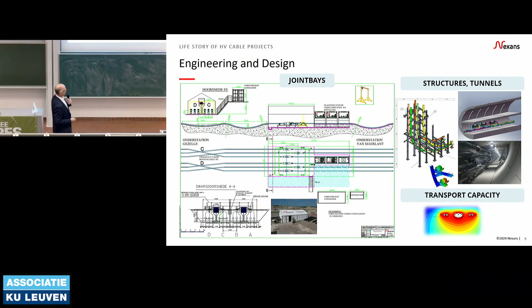And it's even more tricky when you have multiple circuits besides each other, because the standardization doesn't foresee that. With 1, 2, 3 circuits you find it in the standards. Once you go to 10 circuits, if you do not have your own computational model, you fail. You cannot correctly compute the maximal ampacity in the circuits. So it's also demanding in terms of engineering, methods and programs. Each cable manufacturer has his own computation program to correctly dimension the length.